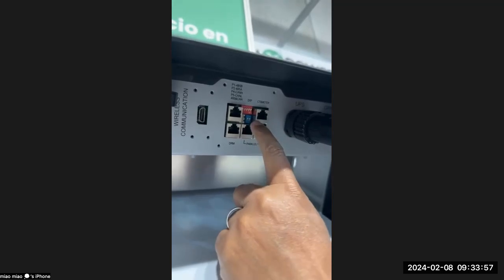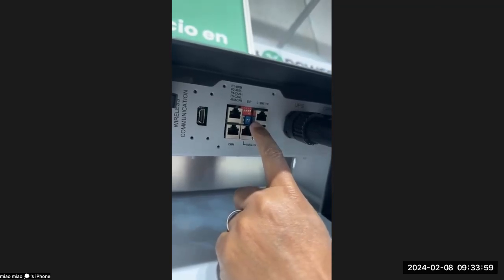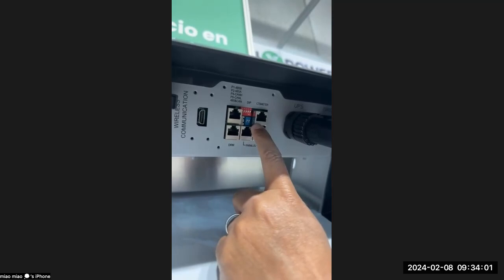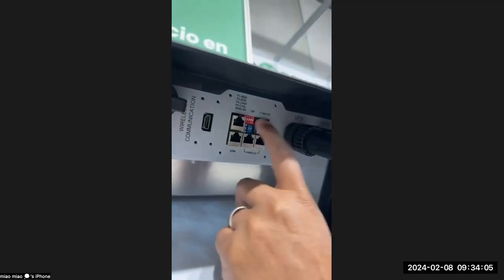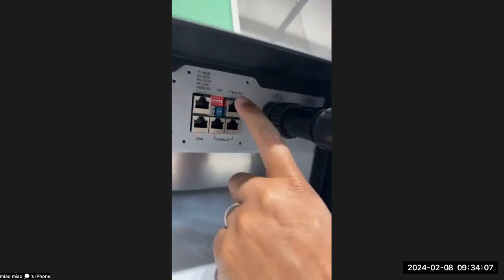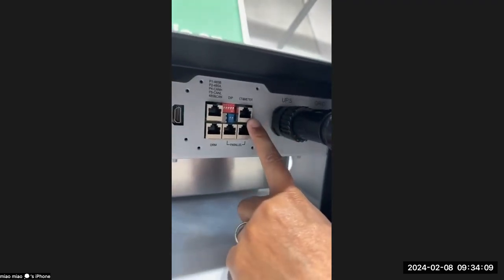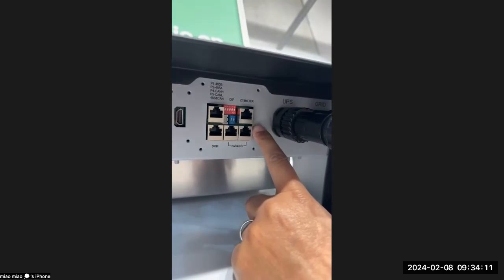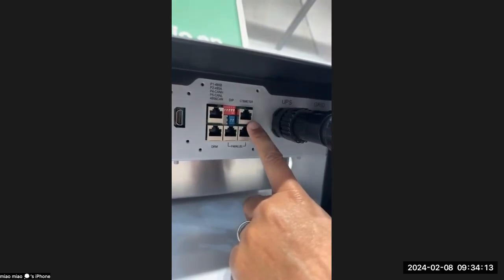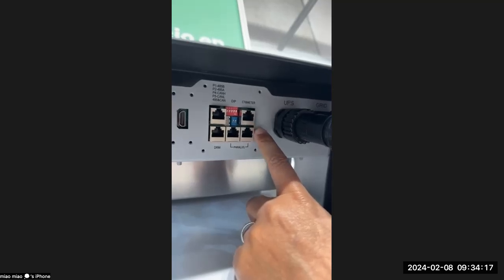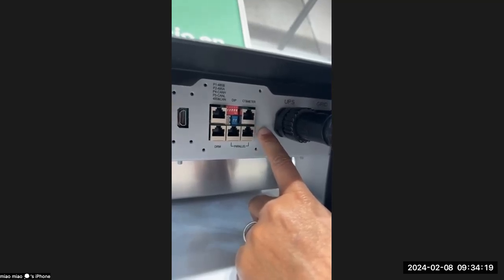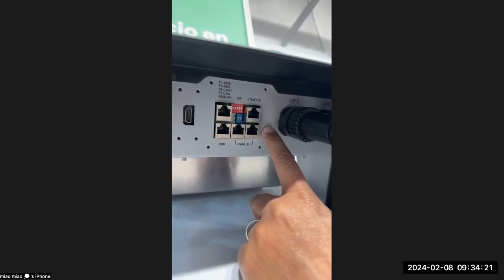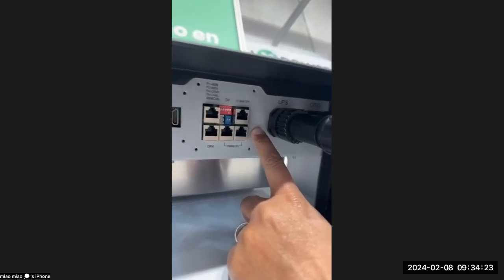Below that, you have your dip switch. This one is blue. You guys are familiar with the old red ones and the blue. So the blue ones are now with the CAN communication, where we're running your CAN on pin 4 and 5. This one is for the CT meter. And with the LXP, you cannot do the installation without the CT. The machine will work without the CT, but the display won't work 100%. And also the sampling won't be great. So whenever you install an LXP5, the 5, the 10, or the 12, you have to install the CT clamp that comes supplied.